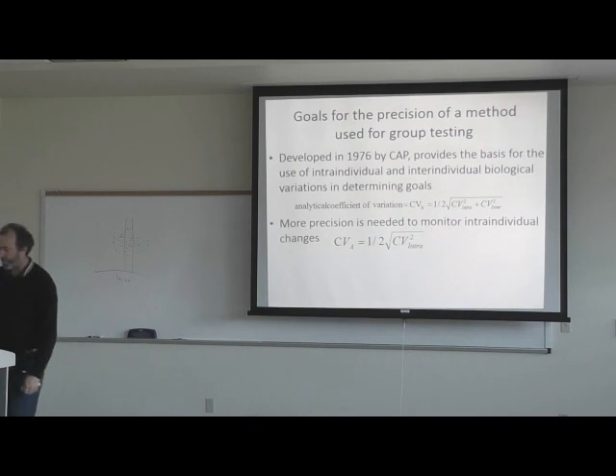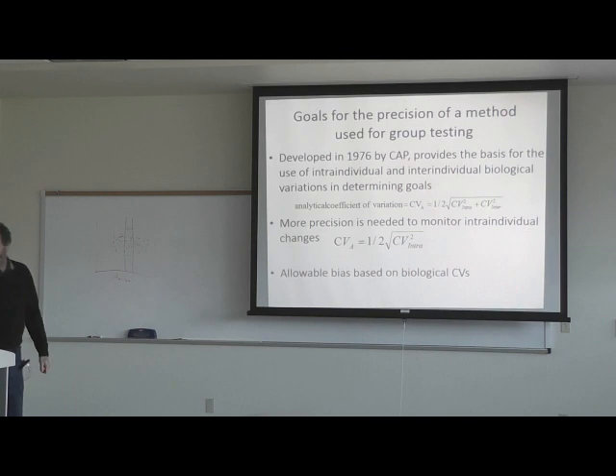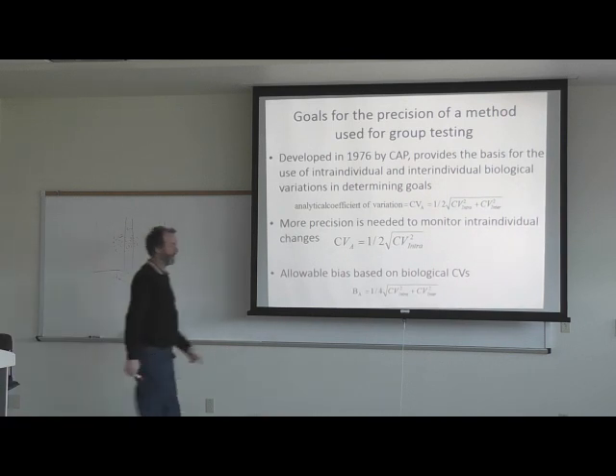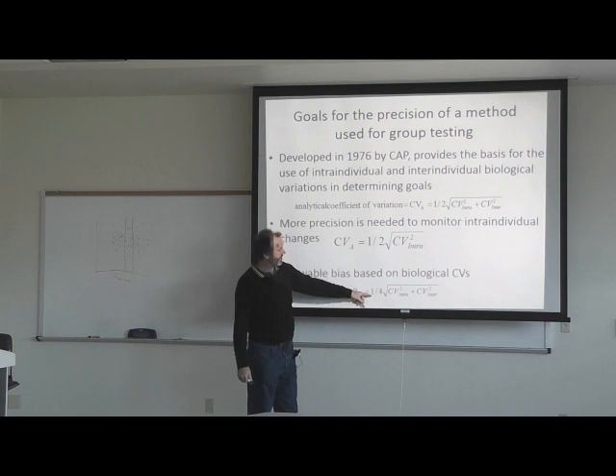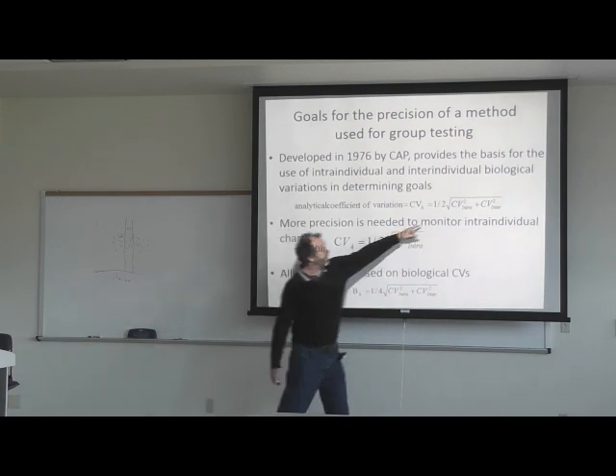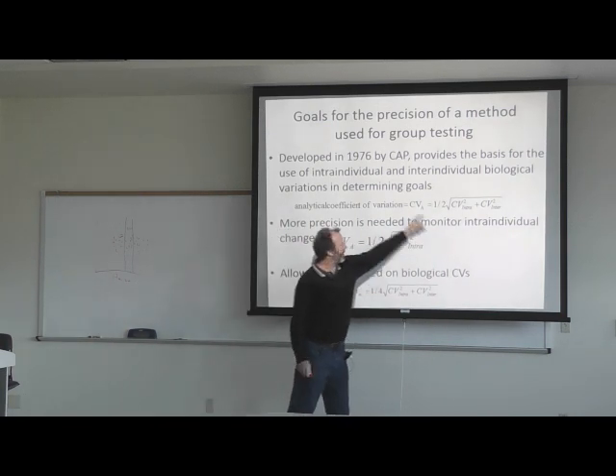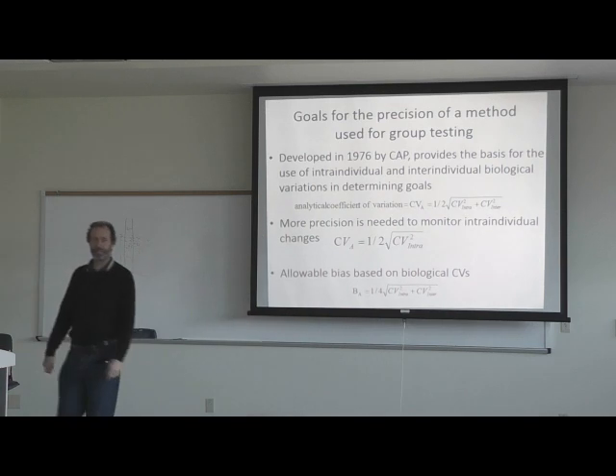The allowable bias based on biological variations — designated BA — is equal to one quarter of the square root of the intra-individual CV squared plus the inter-individual CV squared. If you need more precision for a method, you only look at the intra-individual changes. What is bias? It's a systematic error — the average difference from the true value that the machine has from the real value.